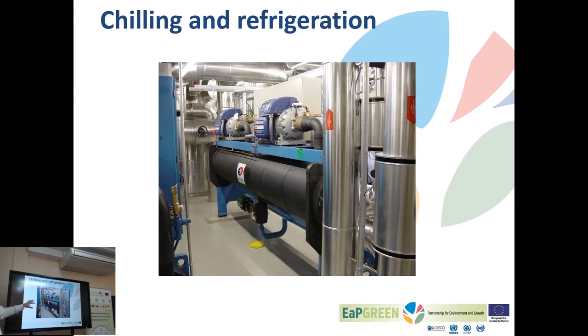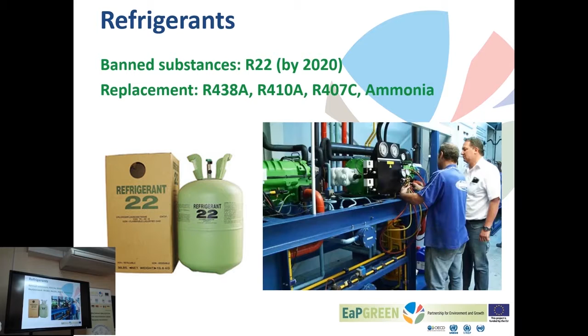First issue is the type of coolant. Not sure whether we need to discuss R22 still, but actually these should be phased out, should be replaced. There are alternatives available from a thermodynamic point of view. A bigger chilling plant should run on ammonia. So whenever we are rebuilding, whenever we are expanding, we definitely should at least consider ammonia. There might be some restrictions, but basically from a thermodynamic point of view, ammonia is what we should choose.